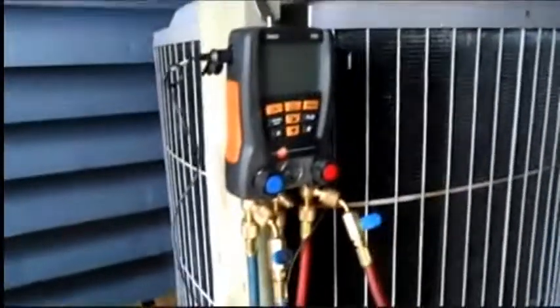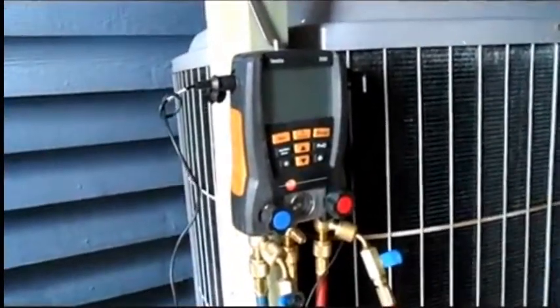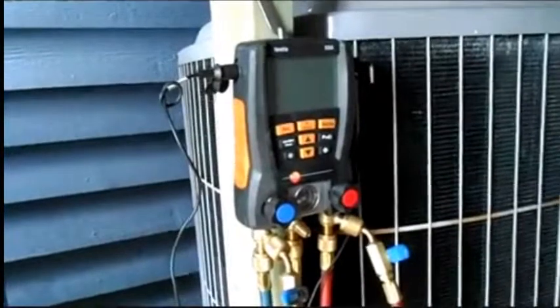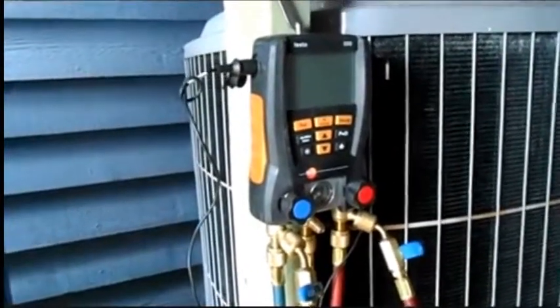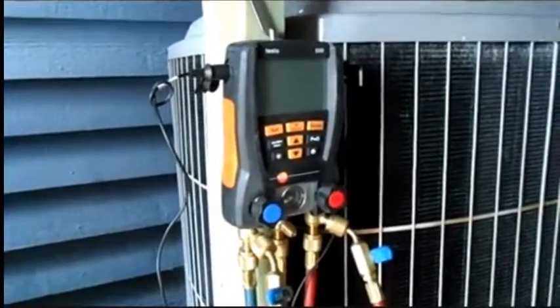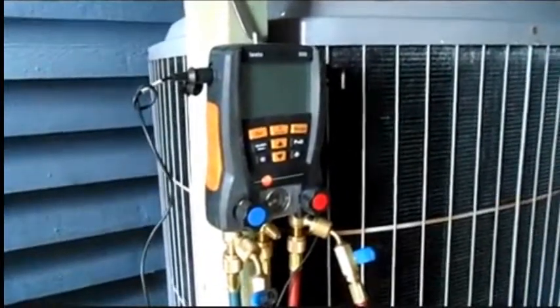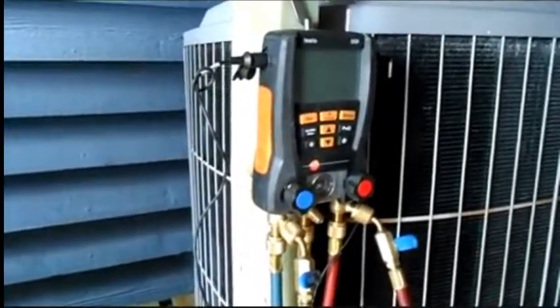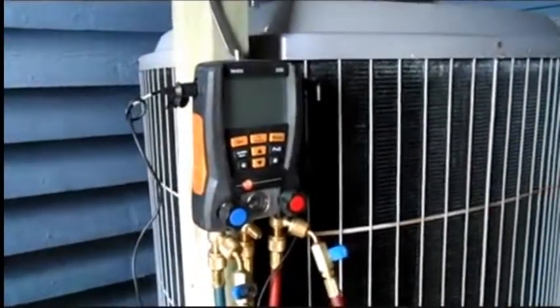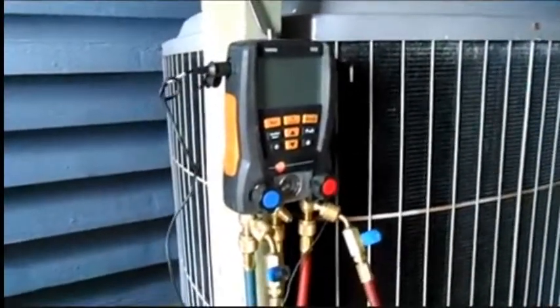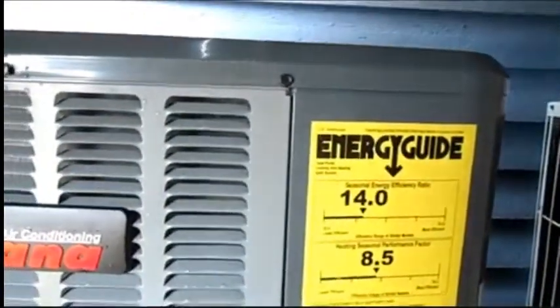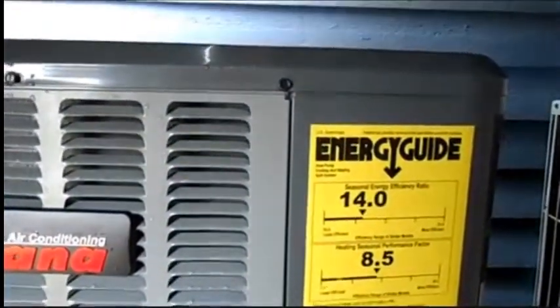So we're all about ready to hook up the testos and weigh in about 20 ounces of charge. We're about 50 degrees outside today. So we're going to weigh in for the line set, which is around 50 foot long. Take away 15 foot for system charge. The machine itself comes charged with 15 foot's worth of refrigerant. You take the remaining 35 foot and you go 0.67 ounces per foot. Roughly that's 2 ounces for every 3 feet.